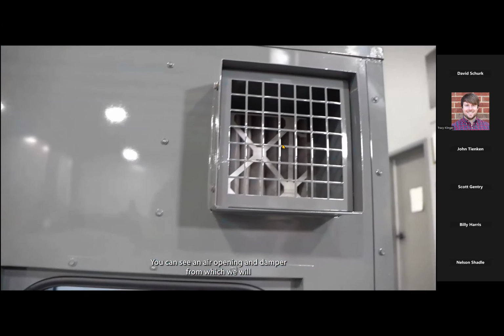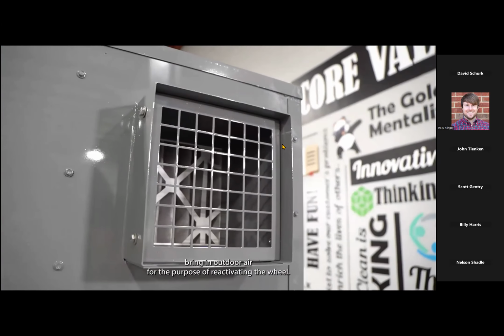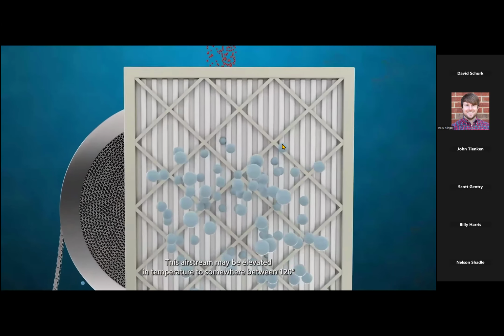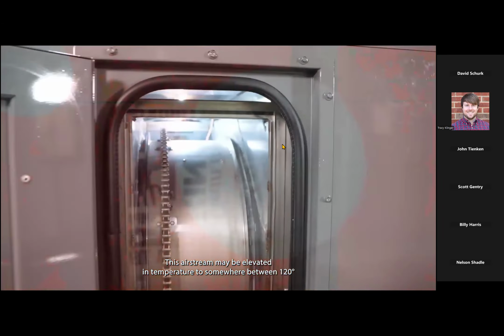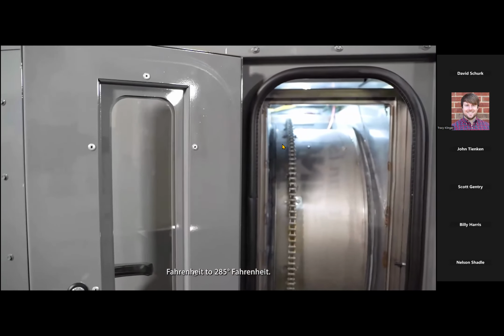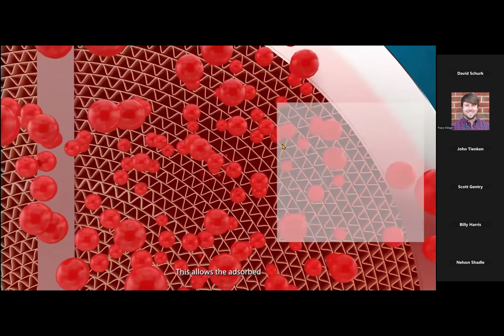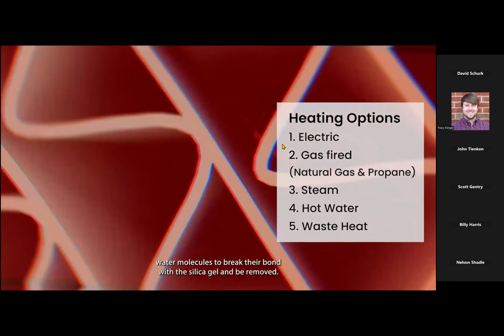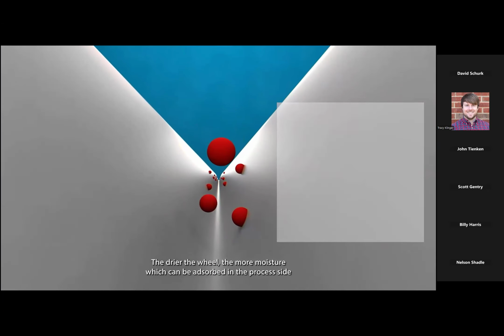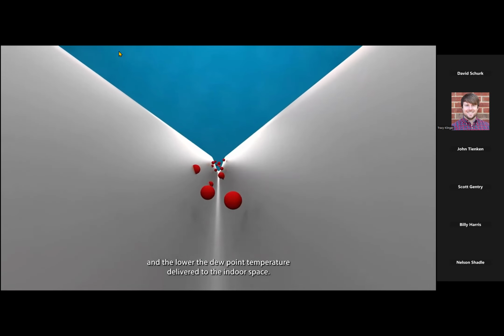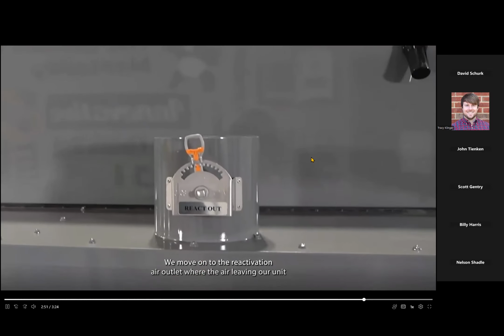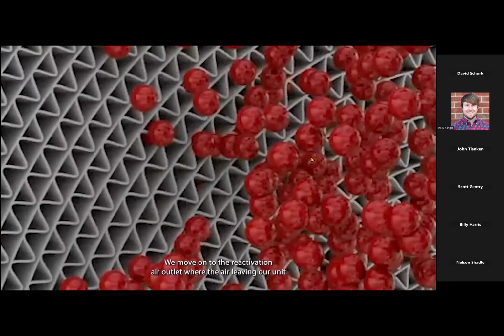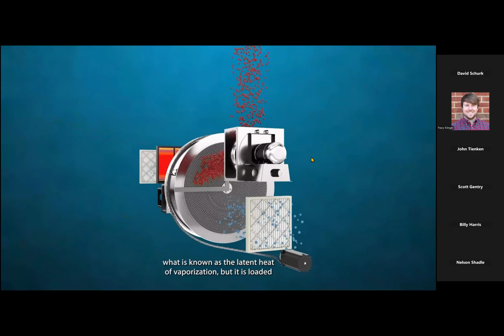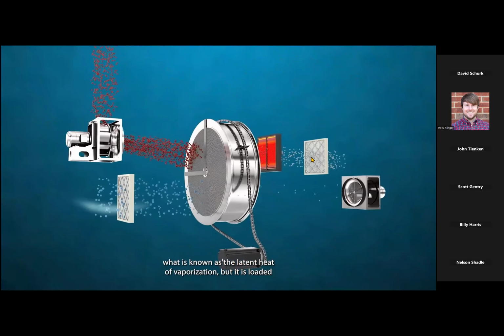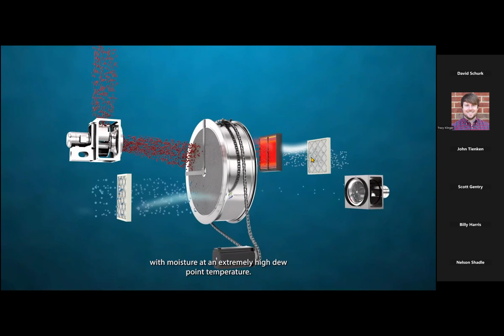You can see an air opening and damper from which we will bring in outdoor air for the purpose of reactivating the wheel. This airstream may be elevated in temperature to somewhere between 120 degrees Fahrenheit to 285 degrees Fahrenheit. This allows the adsorbed water molecules to break their bond with the silica gel and be removed. The drier the wheel, the more moisture which can be adsorbed in the process side, and the lower the dew point temperature delivered to the indoor space. We move on to the reactivation air outlet, where the air leaving our unit at this point has been slightly cooled due to what is known as the latent heat of vaporization, but it is loaded with moisture at an extremely high dew point temperature.